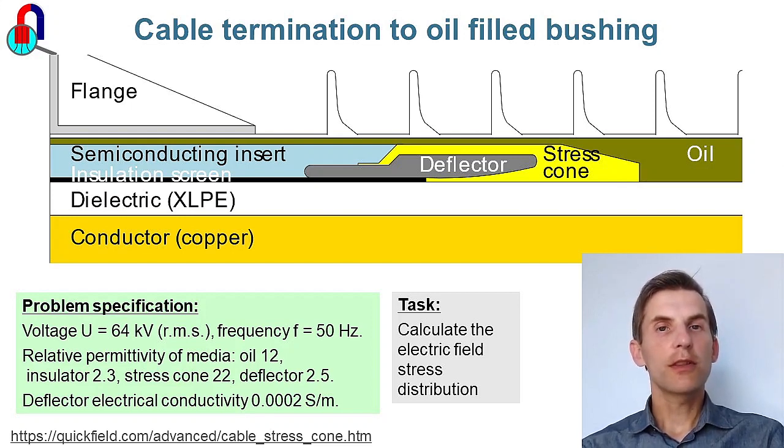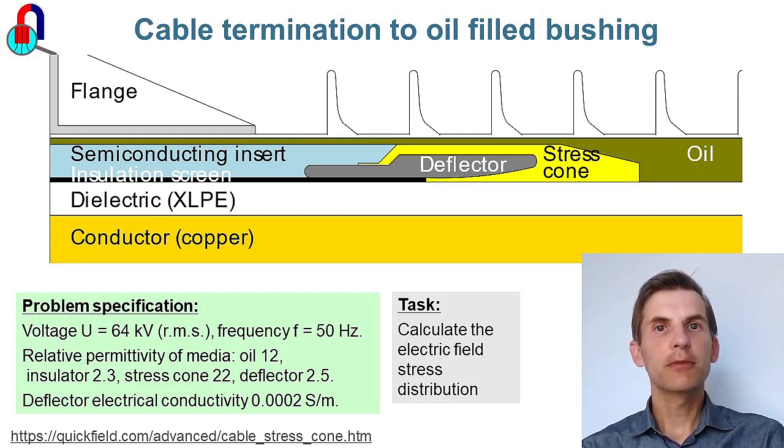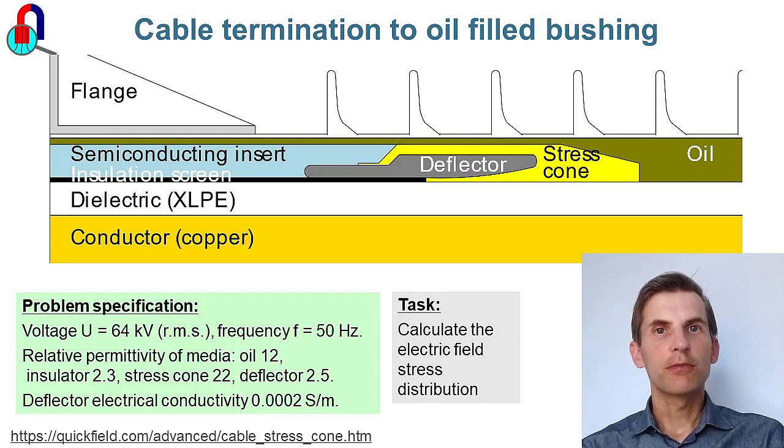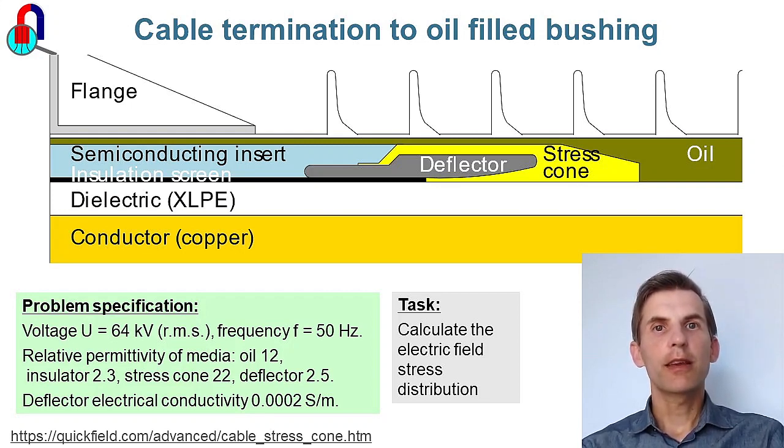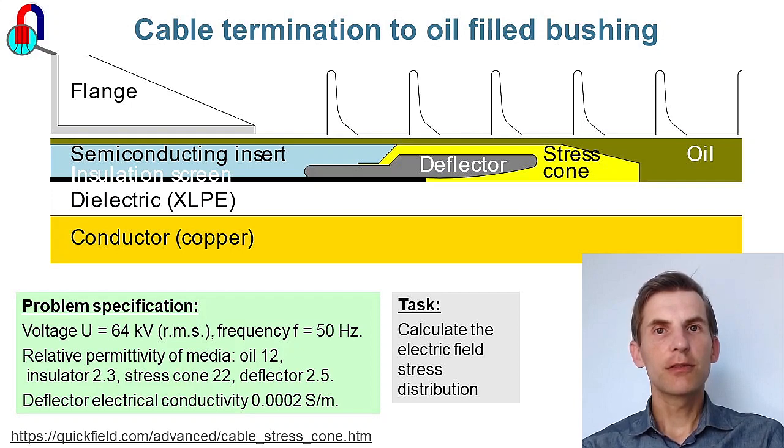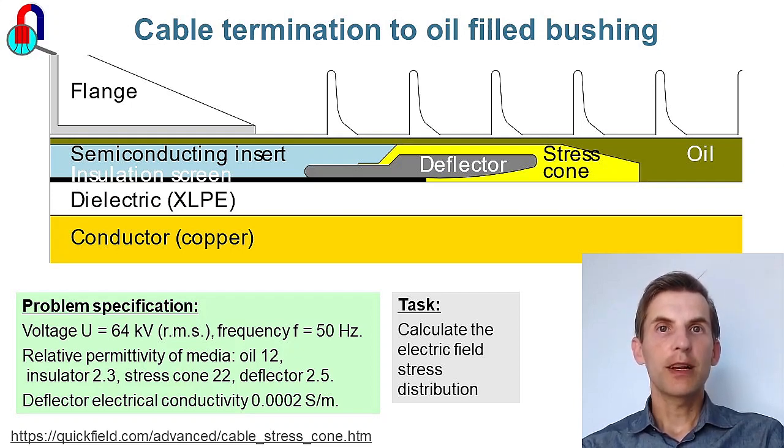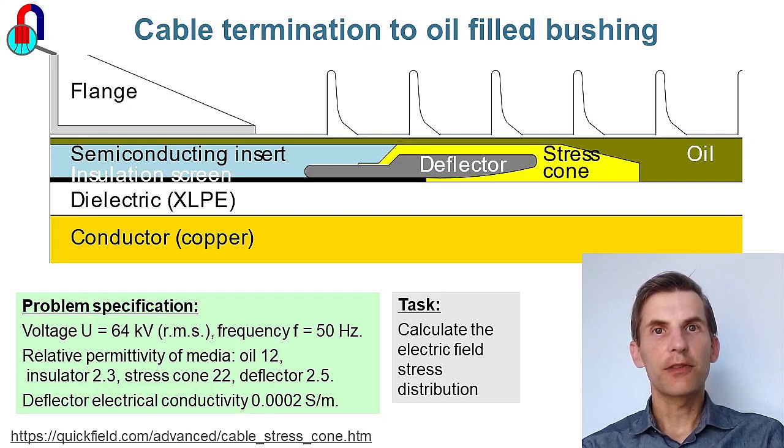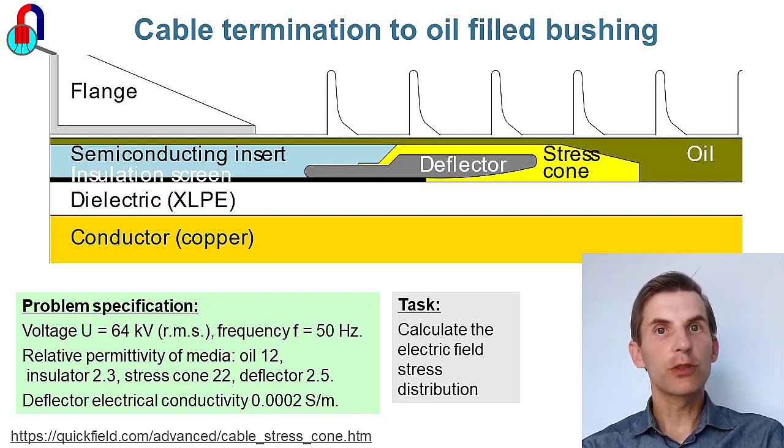To connect the cable to the bushing, we need to strip all cable layers except the conductor. In the place where the cable screen ends, there is a high electric field gradient, high electric field stress, which may exceed the breakdown voltage of the insulation.